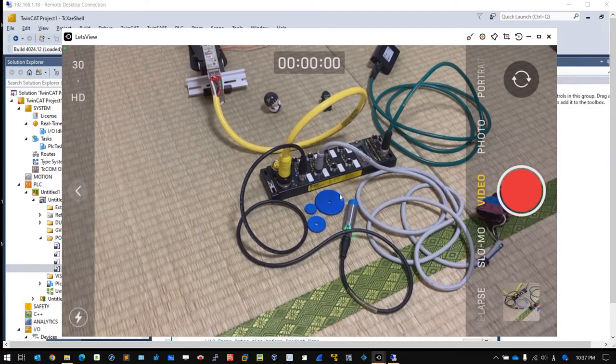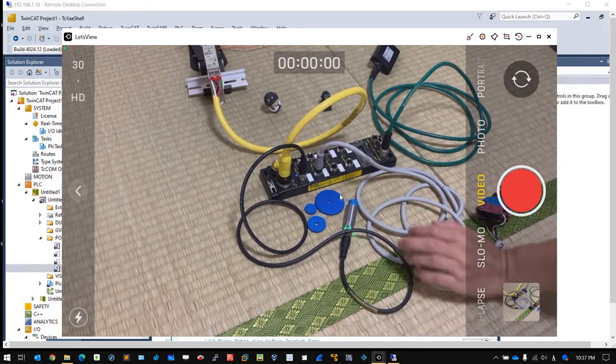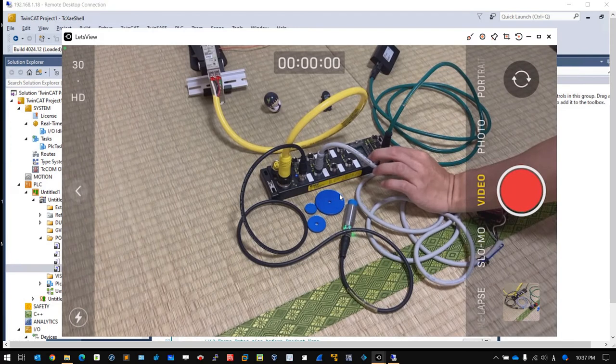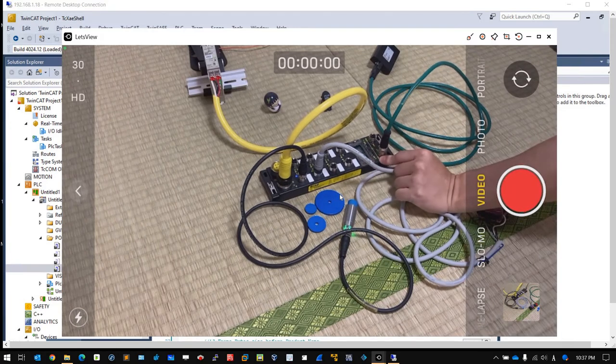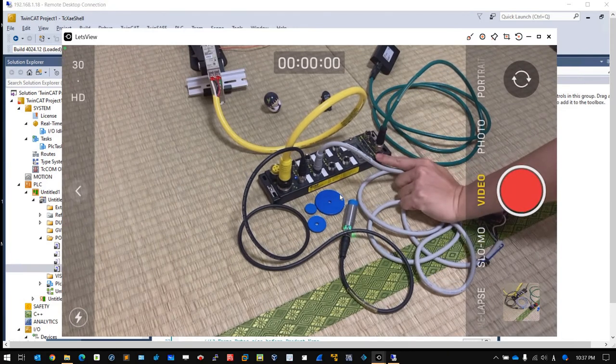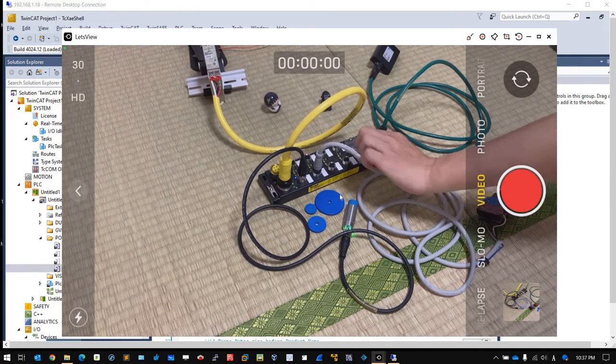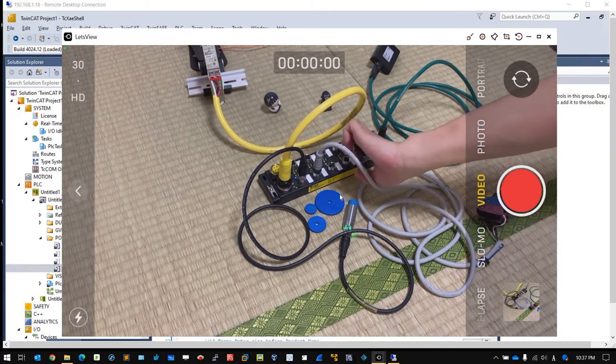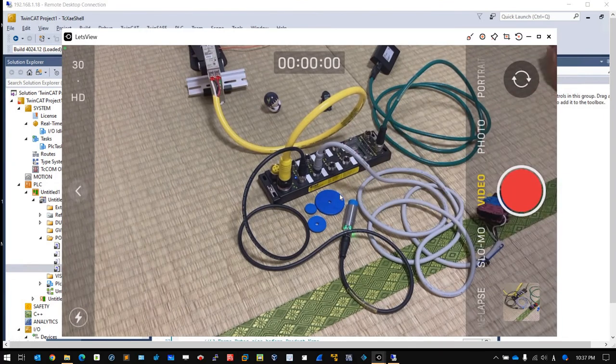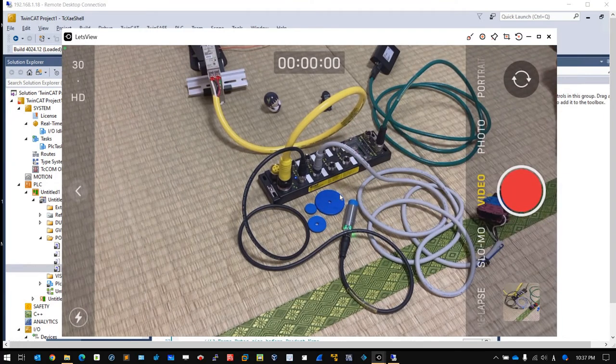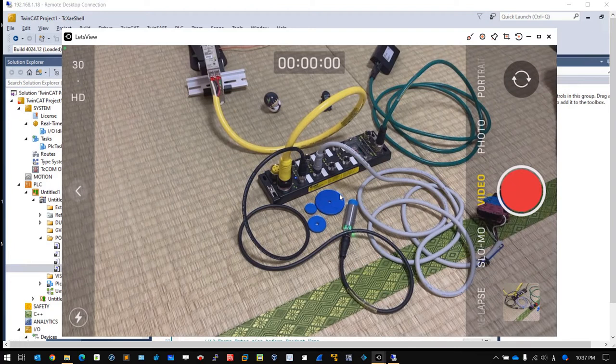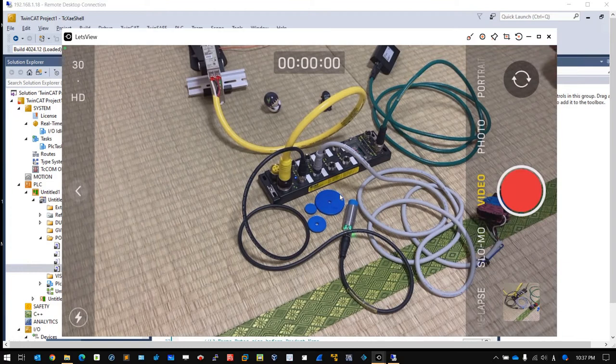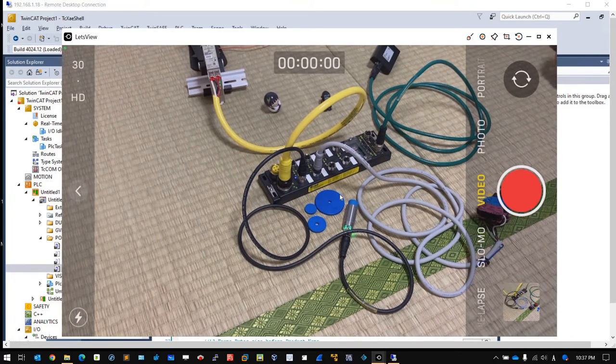I want to explain something about the Ethernet IP. Here you can see a module status LED and a network status LED. This references the CIP standard. If both of these LEDs are turning on and green, it means the adapter and scanner are exchanging real-time data.